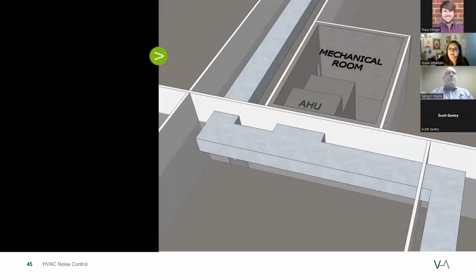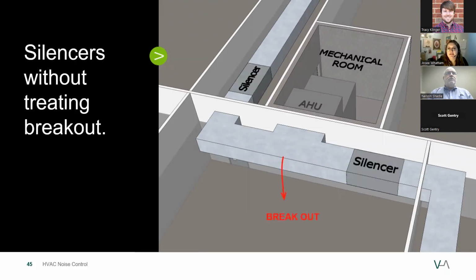So let's take a look at this sketch, and I want you to ask yourself where the best place to put a silencer in the supply side of this system would be. Many times, the silencers would be placed downstream of elbow fittings in a straight section of duct to simplify installation and lower the perceived cost of noise control. But a bigger issue with this is that it's missing the breakout calculation, even though noise control solutions have been designed.